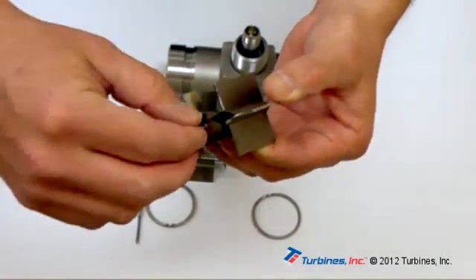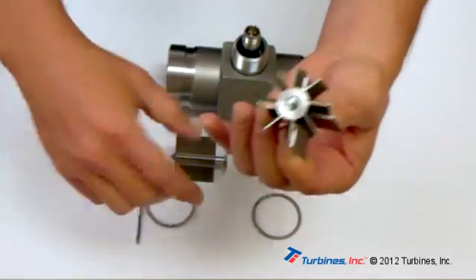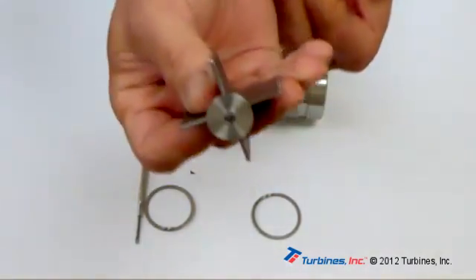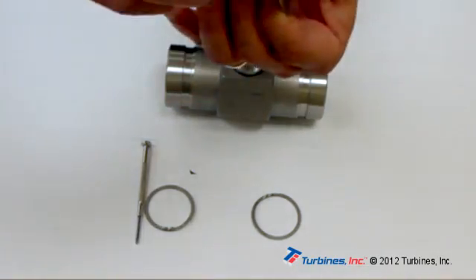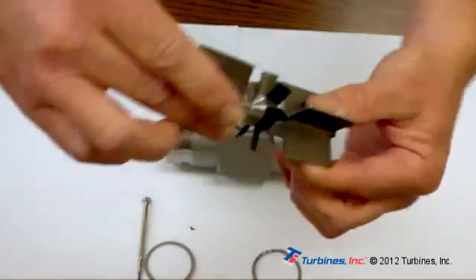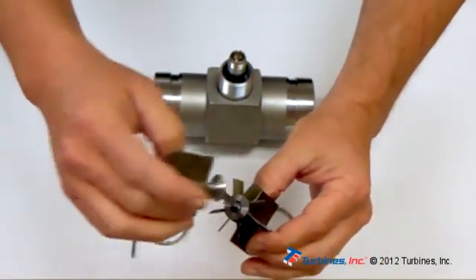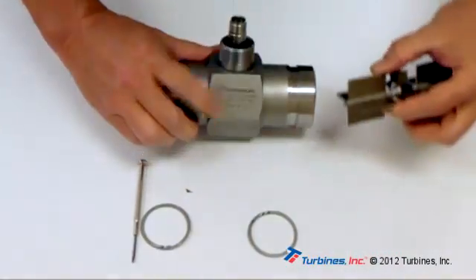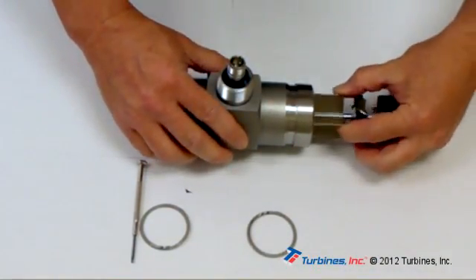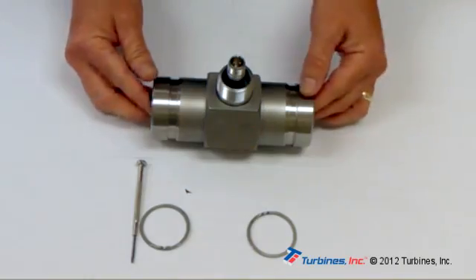The inside of the rotor goes to the shaft side of the cruciform and that should slide on fairly easily. And then the other cruciform fits directly and you will see that there is a location for the shaft to come across into the cone and that fits right on top of the rotor. Now we will locate our arrow and make sure that the inside of our rotor on the shaft side goes to the inside of the housing. That slides right inside and sometimes there might be a little friction there, but make sure you can just push that in with your hand.